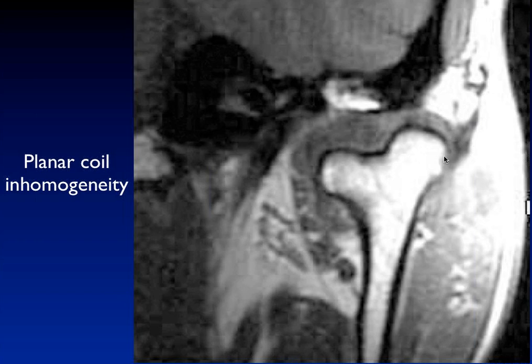Here is a planar coil placed next to the temporomandibular joint — we can see the condyle right in the center of the image. Notice that with a planar coil, you're very sensitive to signal close to the coil, but it drops off fairly rapidly. This gives very poor signal-to-noise on one side of the image and very high signal-to-noise on the other. This lack of homogeneity makes single-loop coils non-optimal, though we worked with them for many years.